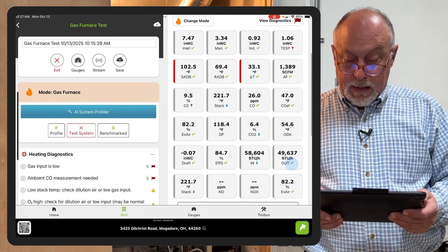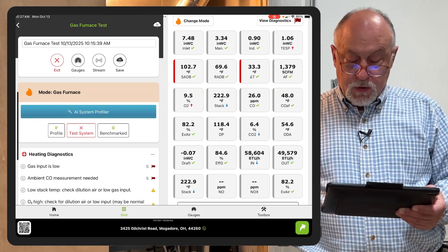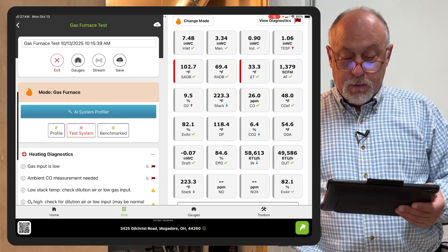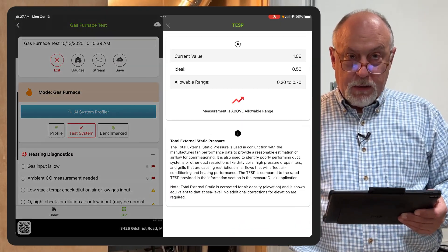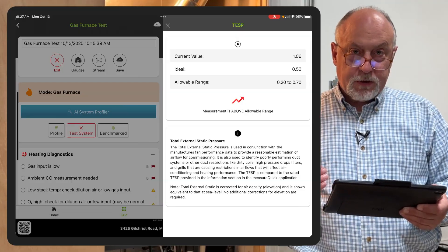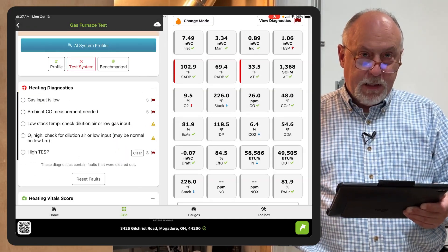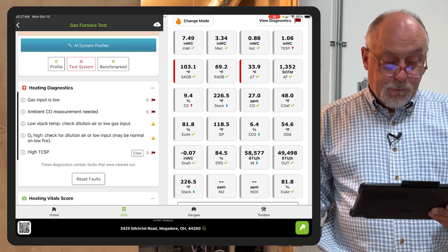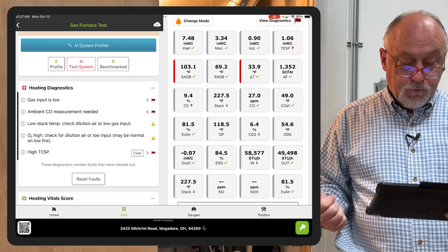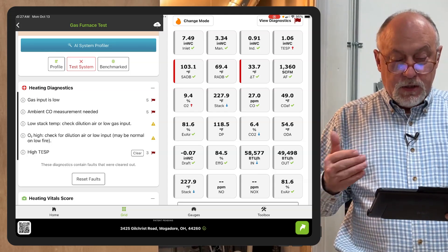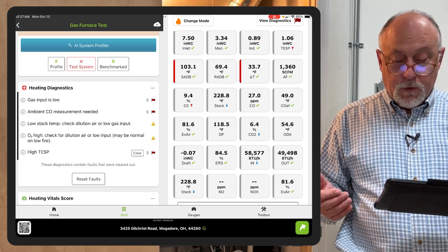Right now you can see that I have a low manifold pressure at 3.34 inches. It's within acceptable, but it's resulting in a little bit low gas heat input, which I could dial up. You can see I have a high static pressure. If I tap on any one of these, it'll tell me what the total external static pressure is and how it's used. On the left-hand side of the screen, it's looking at our gas inputs low, CO ambient temperature's noted, low stack temperature, high O2, and high static pressure. So diagnostics are now built in for the combustion analysis as well as the furnace.